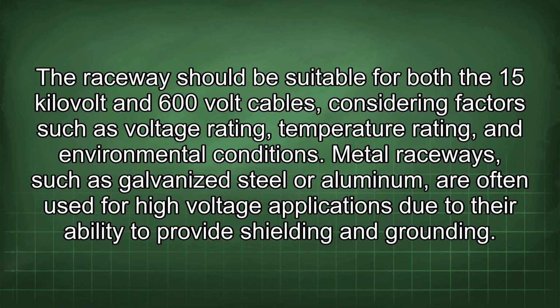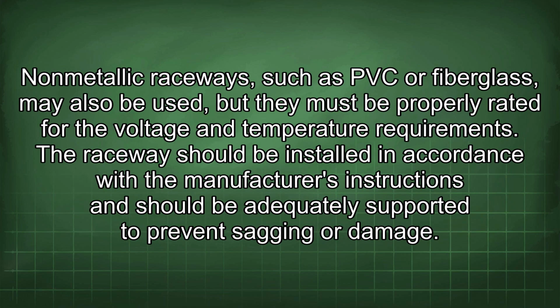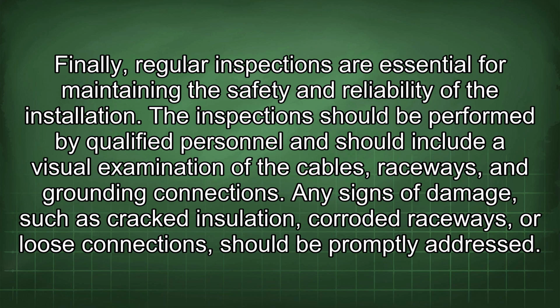Metal raceways, such as galvanized steel or aluminum, are often used for high voltage applications due to their ability to provide shielding and grounding. Non-metallic raceways, such as PVC or fiberglass, may also be used, but they must be properly rated for the voltage and temperature requirements. The raceway should be installed in accordance with the manufacturer's instructions and should be adequately supported to prevent sagging or damage. Finally, regular inspections are essential for maintaining the safety and reliability of the installation.